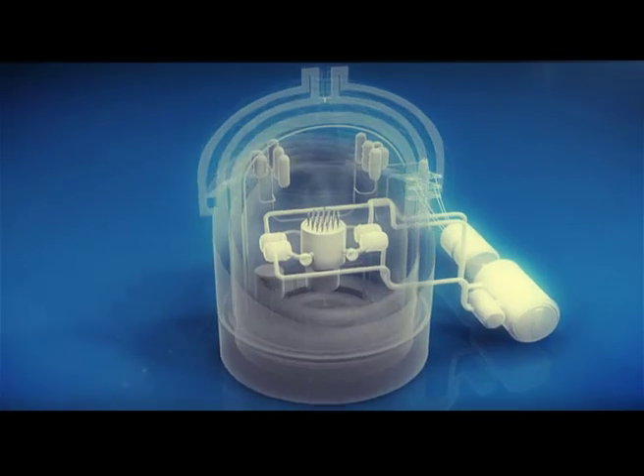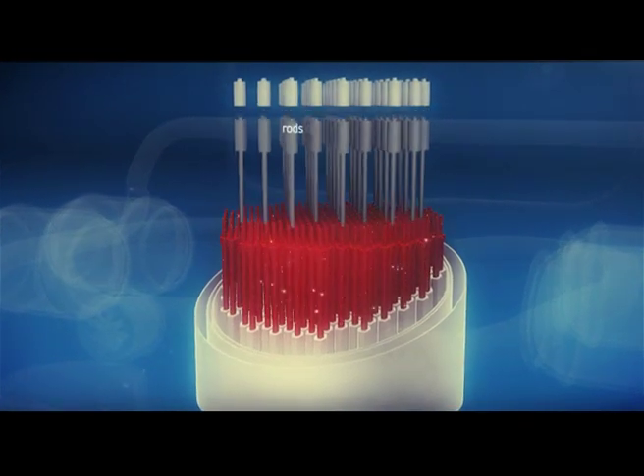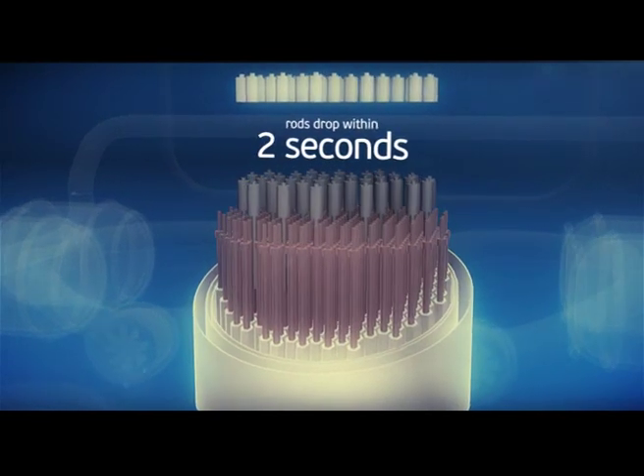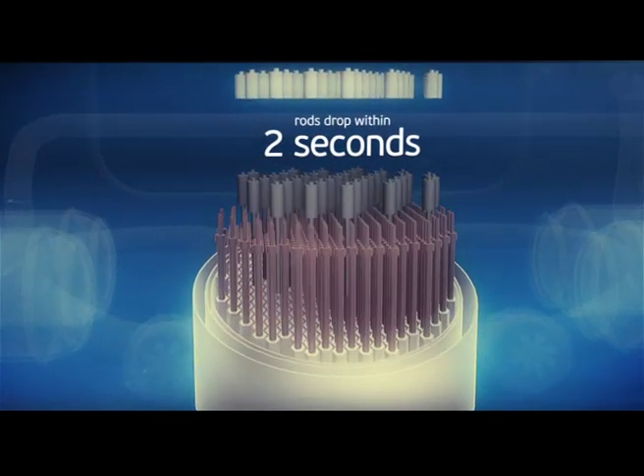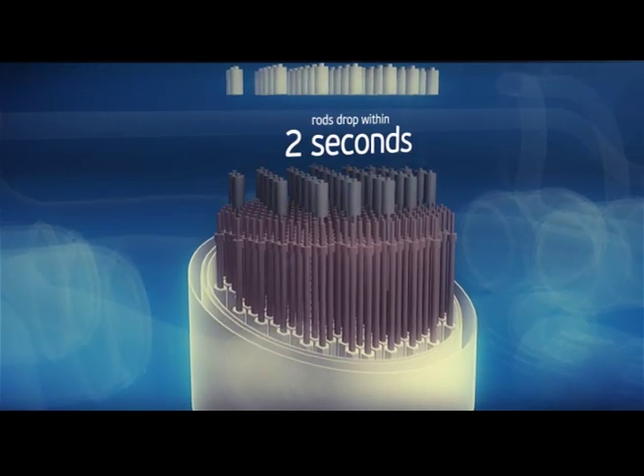In emergencies, to terminate the nuclear reaction, boron carbide scram rods are inserted into the reactor core. The rods are hanging over the core kept by electromagnets and drop by own weight within two seconds. The rods absorb neutrons and the chain reaction terminates.